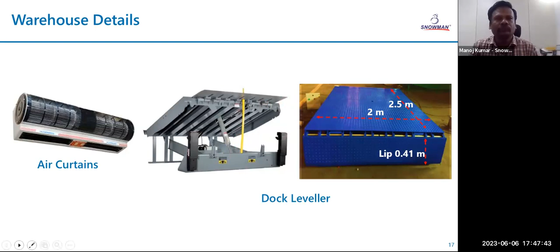So again, complete India details we are giving now. Total number of warehouses is 43, total number of chambers is 302, and the total refrigeration load - about 350 to 400 kilowatt each warehouse - comes to 9 megawatt in electrical load. Our consumption, unit-wise, is 3.5 crore units per year, costing 30 crore per year. That is 15% of the company's storage revenue. So if you store material monthly, 15% of what you collect is the power cost. I want to tell the industry there's a very big potential here - through various initiatives and activities this can be reduced further, which we also do, and I'm covering that in this slide.